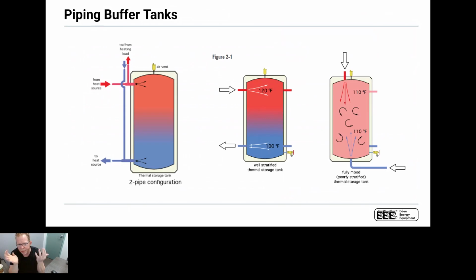From the standpoint of piping buffer tanks, this is, again, just some typical piping configurations. The one on the far right-hand side is an absolute no-no. You have to be careful dumping into the top of the tank. There are caveats. Some tanks, when you feed into the top, will have a dip tube with a diffuser on the bottom. There's different ways to get around it. But the key thing is we want to make sure we have a stratified tank.